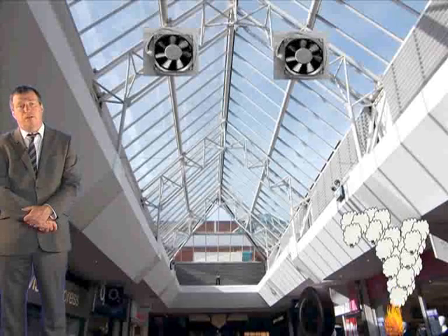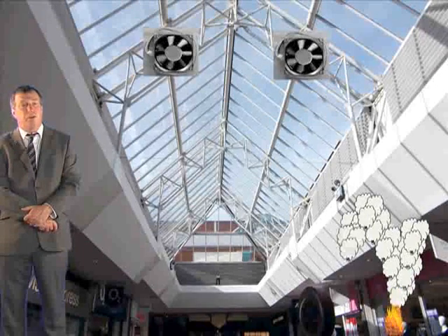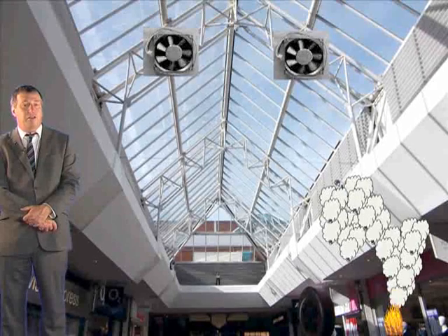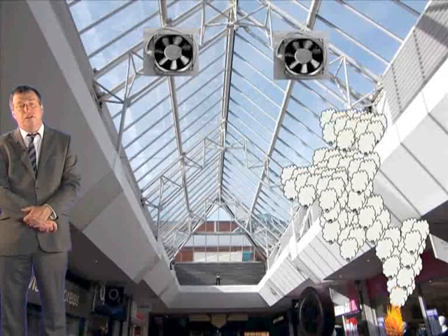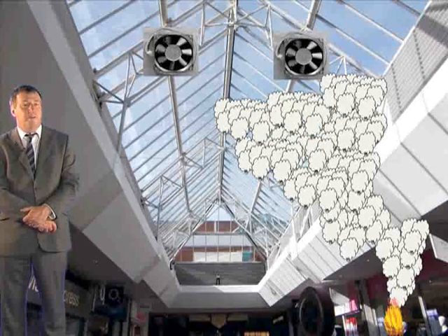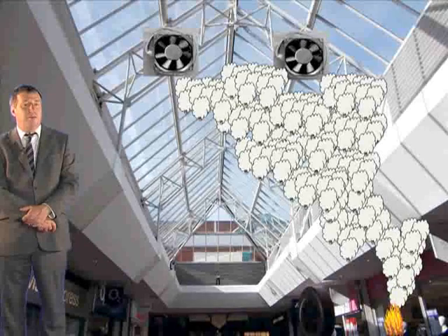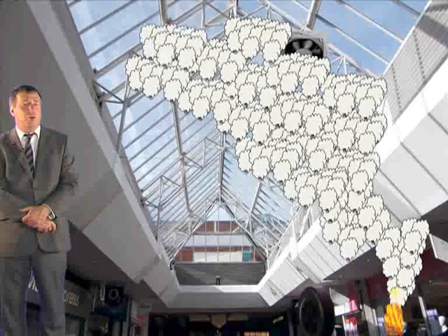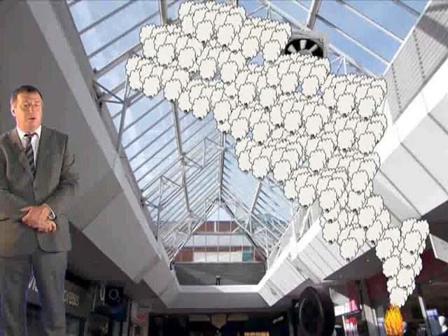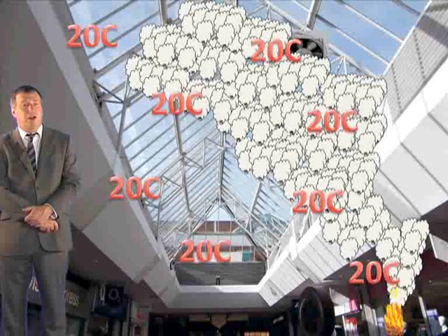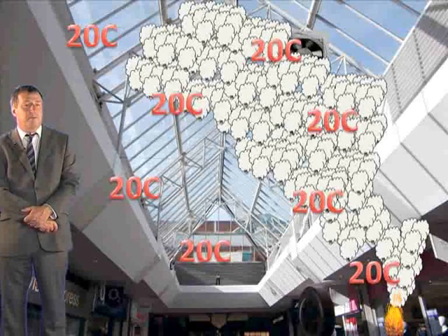One of the requirements of a smoke control system of this type is that the smoke rises to the ceiling to form a distinct smoke layer under that ceiling. The smoke will only do this if it is sufficiently buoyant. In other words, if it's sufficiently hot. Therefore, there is a minimum temperature rise below which it is considered that smoke will have insufficient buoyancy to form the required smoke layer at ceiling level. And this minimum temperature rise is 20 Kelvin or 20 degrees C.